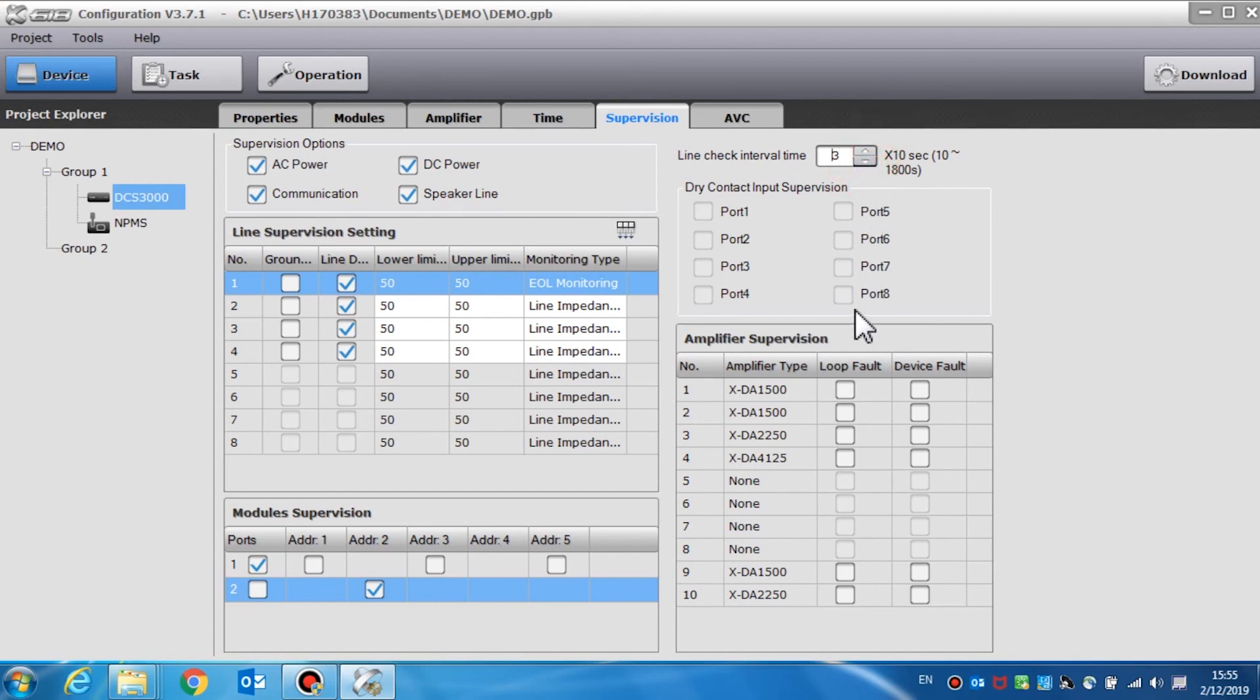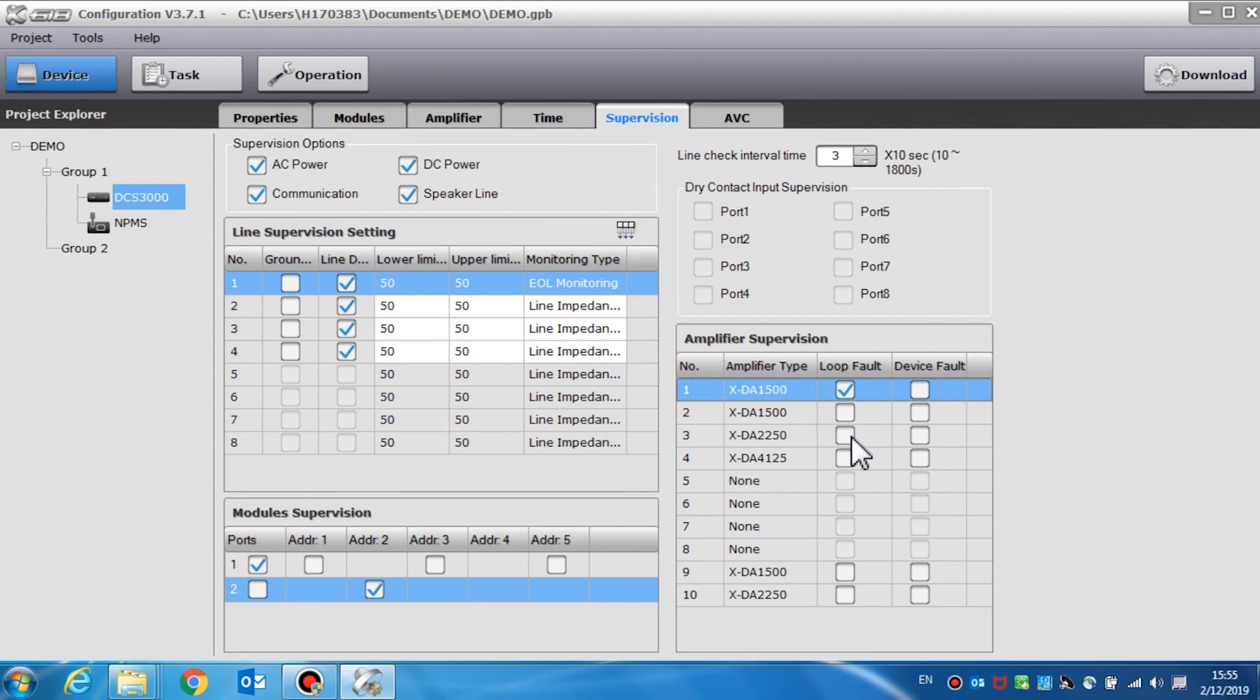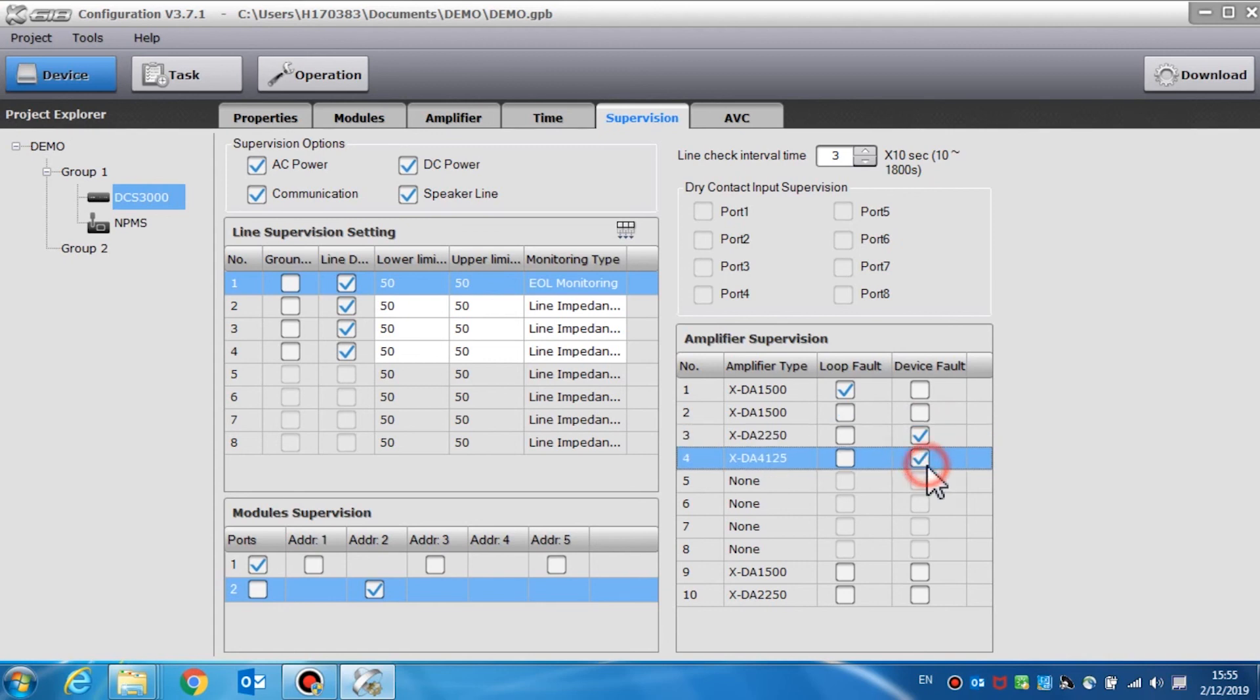Amplifier supervision is used to supervise the device fault and the loop fault of the amplifier. If it is needed, a device fault will indicate a fault in the amplifier, such as the power fault or protection circuit fault.